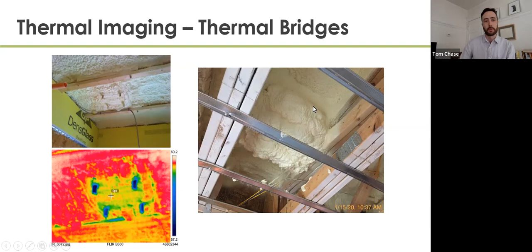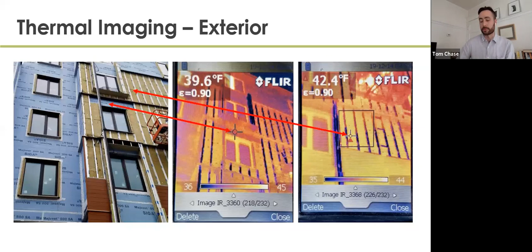We also do thermal imaging of the exterior, and this is a really interesting photo. Without going into all the detail of thermography's art and science, basically what we're showing is that the air barrier and continuous insulation are performing as expected. On very large buildings, the air barrier is responsible for most of the thermal control, and the continuous insulation outboard of that is what's needed to get you over the hurdle to a really exceptional performing building under the passive house standards. So what we see here is that most of the work is being done by the air barrier—it's not showing leaks, even as the building is being temporarily heated in these images—and the continuous insulation outboard is doing its job as well.